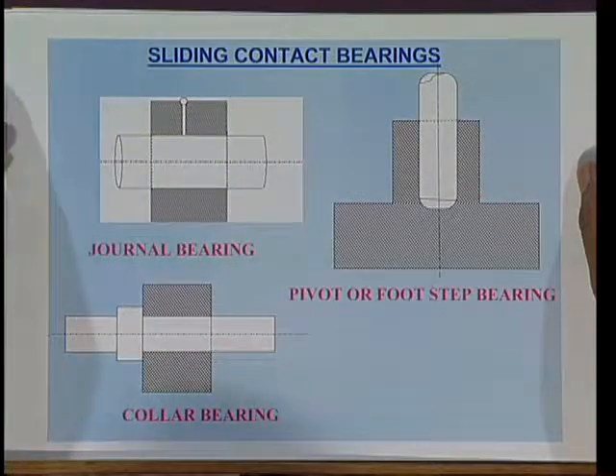Let us go to another type of bearing: the sliding contact bearing. In sliding contact bearings, there is no need for rollers or balls. Only two surfaces make sliding contact. To reduce the friction between the two surfaces, a lubricating oil or other grease is used. For fractional motors, self-aligning porous bronze bushes are used. For larger motors, journal bearings are generally used.